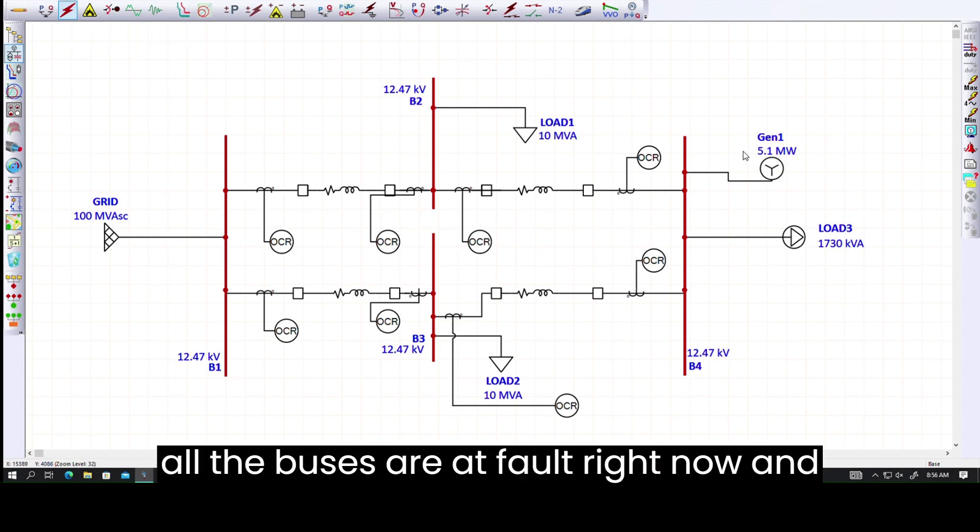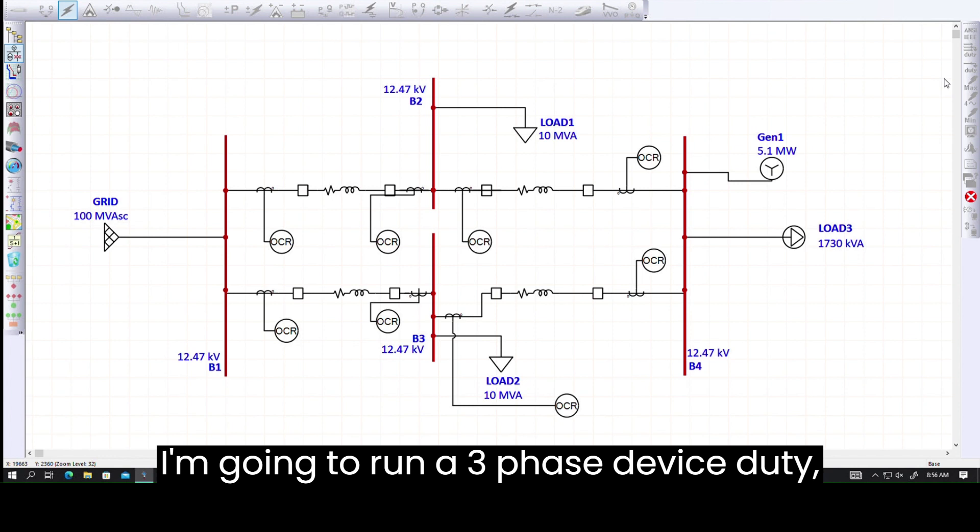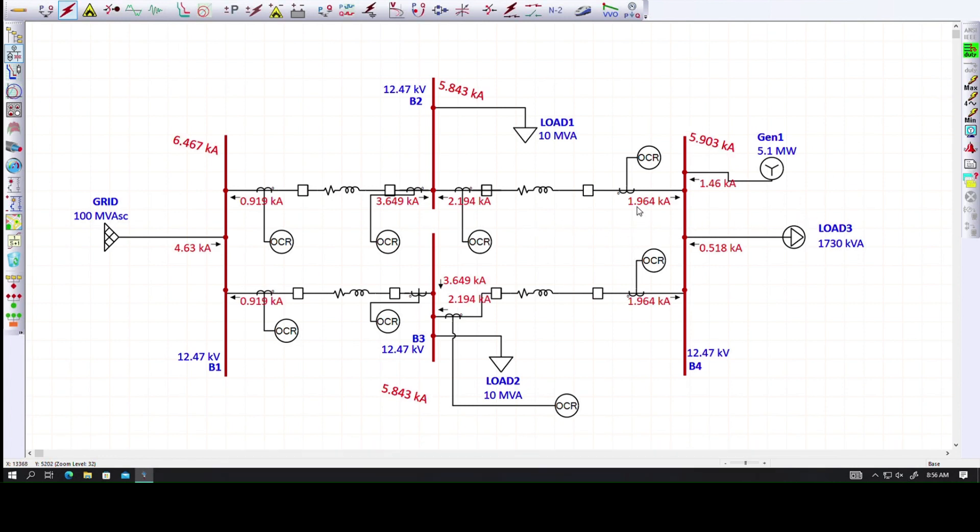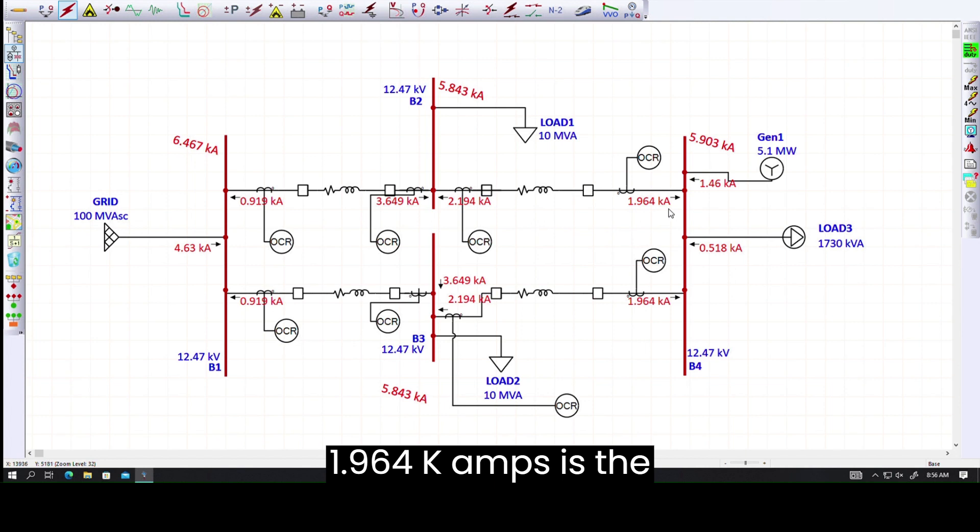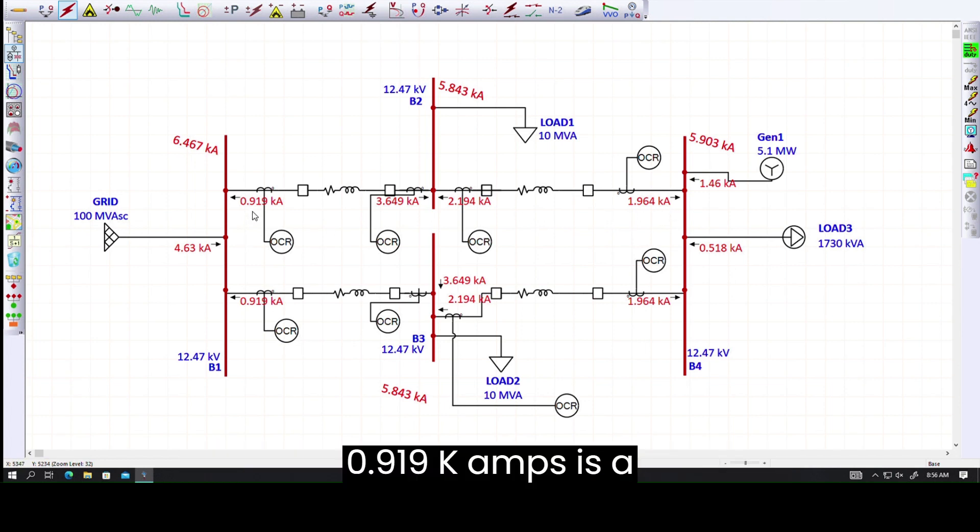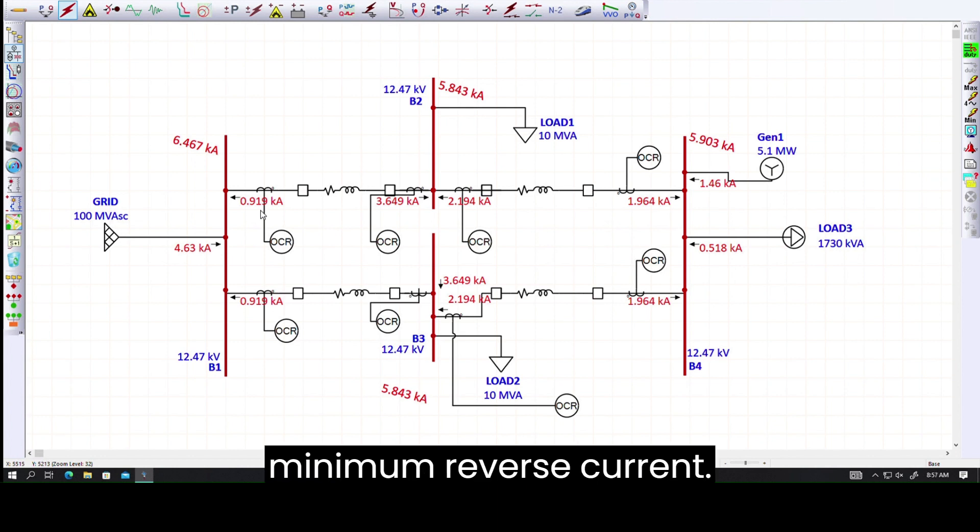Now all the buses are at fault right now and I'm going to run a three-phase device duty. Here we figured that 1.964 kA is the minimum forward fault current and 0.919 kA is the minimum reverse current.